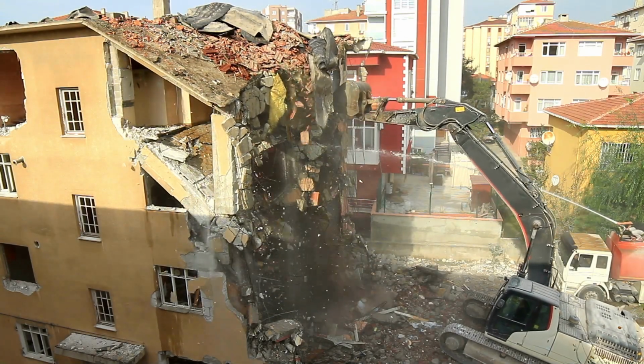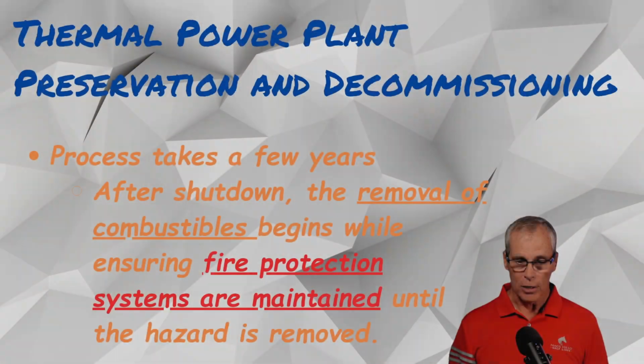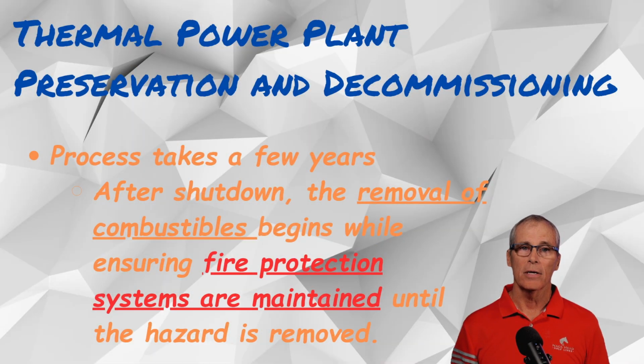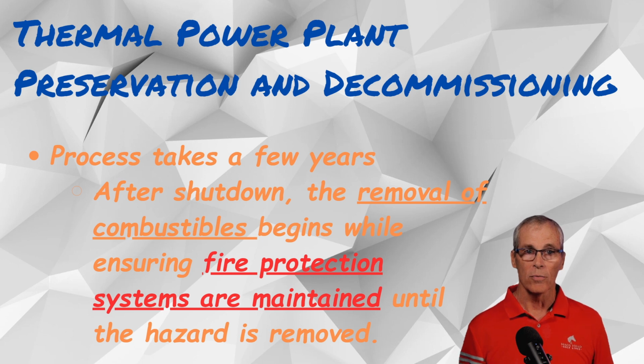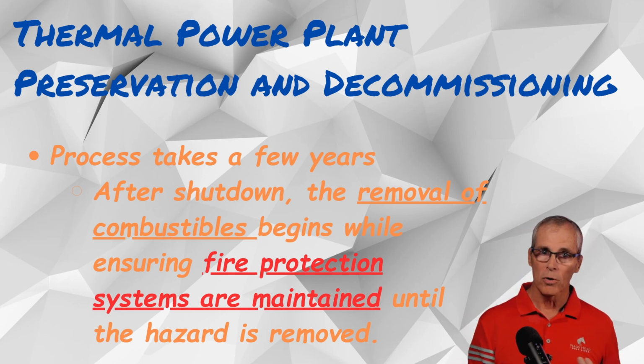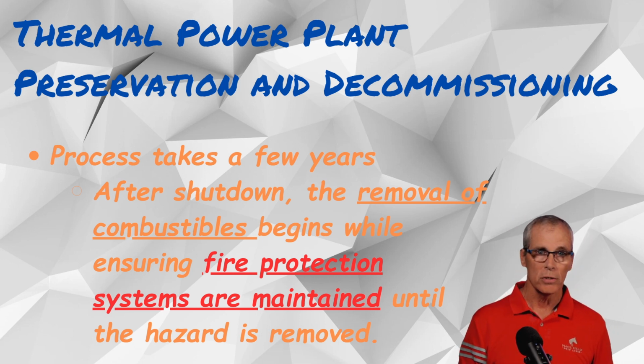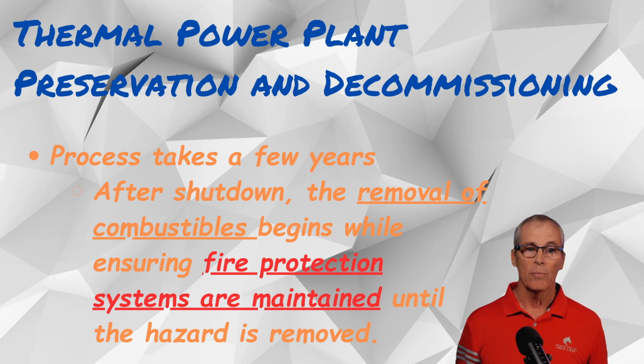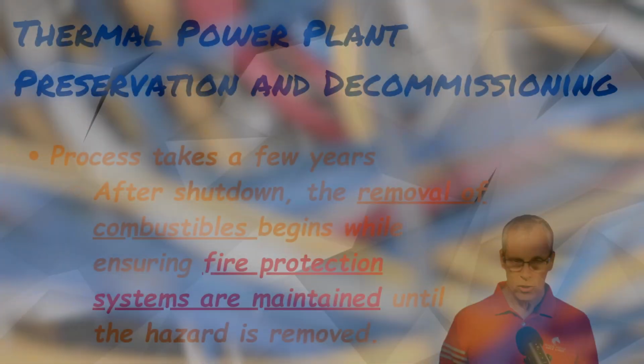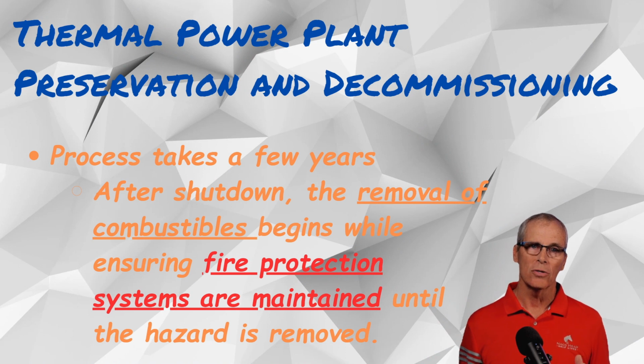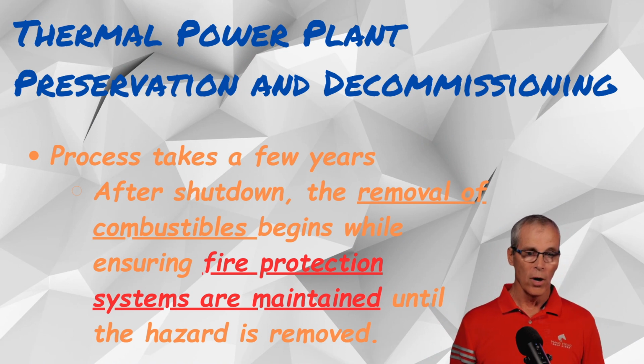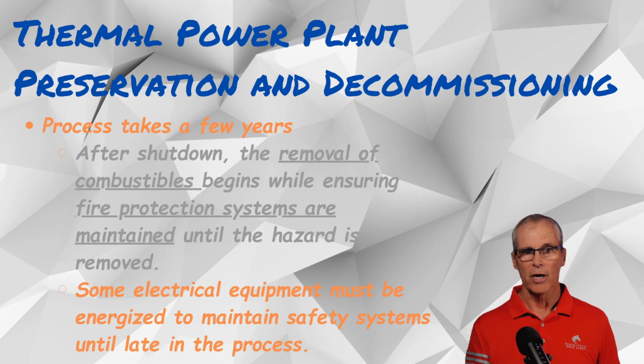The first thing you have to do is remove the combustible material and hazardous materials. That's not as hard as it sounds, it just takes time. You have to remove all the lubricating oils, fuels that have to be purged out of piping, potential plastics in cable trays, and battery rooms full of plastic. There are numerous hazards that have to be removed before we can take the fire protection systems out.